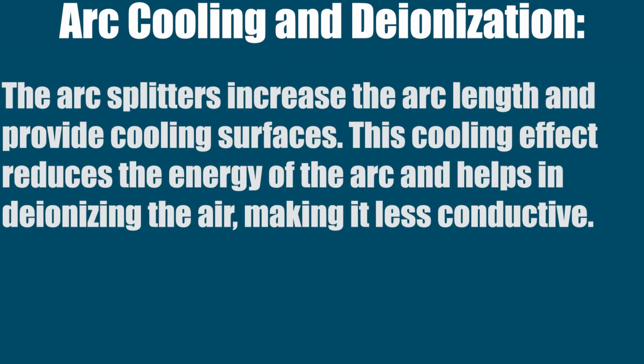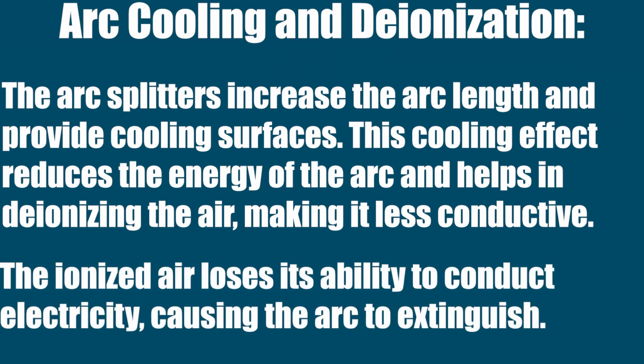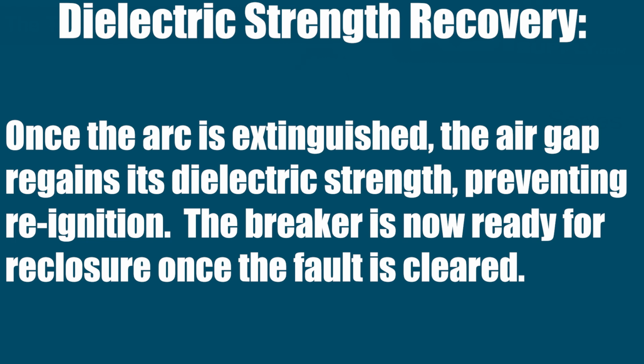Then we have arc cooling and deionization. The arc splitters increase the arc length and provide cooling surfaces. This cooling effect is going to reduce the energy of the arc and help in deionizing the air, and this makes it less conductive. So then the ionized air loses its ability to conduct electricity, causing the arc to extinguish. We have then dielectric strength recovery. Once the arc is extinguished, the air gap regains its dielectric strength, preventing reignition. The breaker is now ready for reclosure once the fault is cleared.